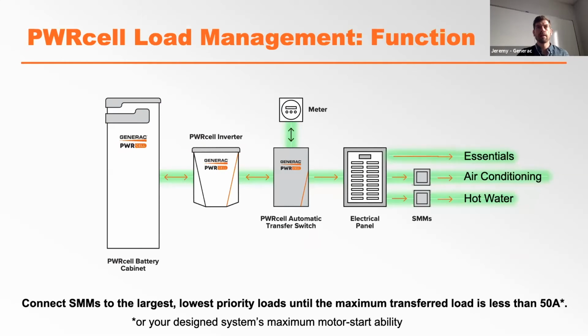Here are some of those components again, but arranged in the way that you would probably actually see them. When the grid goes down, the automatic transfer switch, or ATS, is going to start islanding away from the grid. So you see that we lose this connection right here. Essential loads are prioritized and should never lose power. That's what we see here. The essentials are going to stay up. They're going to stay green through everything that we see here.